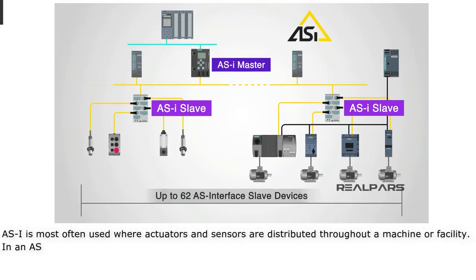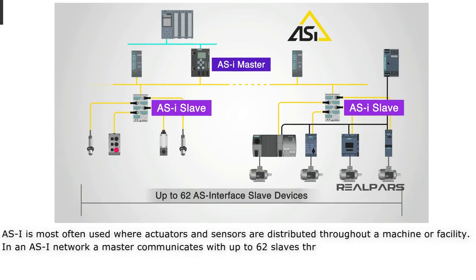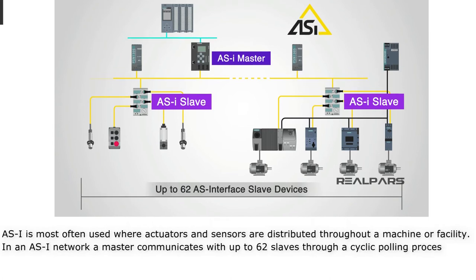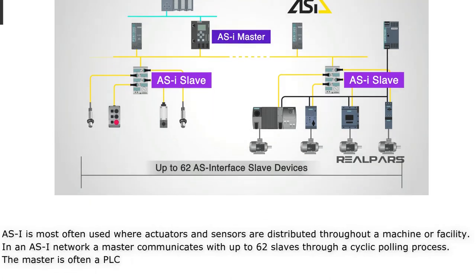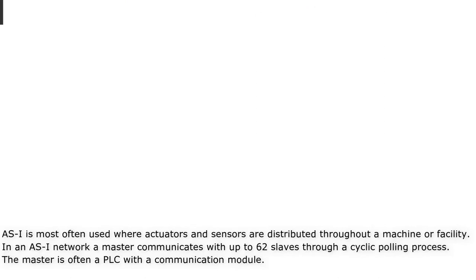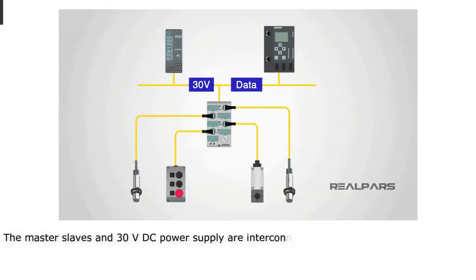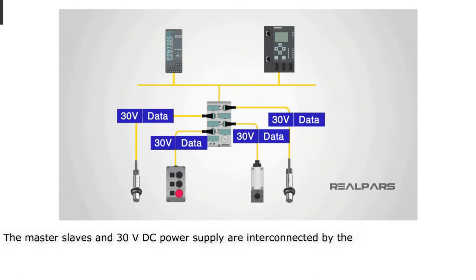In an ASI network, a master communicates with up to 62 slaves through a cyclic polling process. The master is often a PLC with a communication module. The master, slaves, and 30 VDC power supply are interconnected by the two-wire ASI cable.